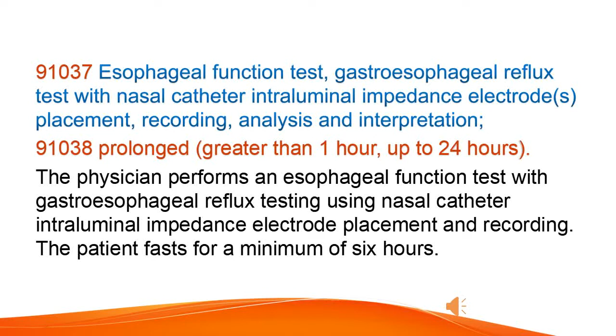An impedance probe affixed to flexible nasal catheter tubing is inserted through the nose down to the lower esophageal sphincter following location of the lower sphincter by manometry. The impedance probe contains several electrodes that make up multiple measuring segments, each 2 cm in length. The measuring segments are located at intervals above the proximal border of the lower esophageal sphincter. The patient is given a liquid or solid bolus to swallow.